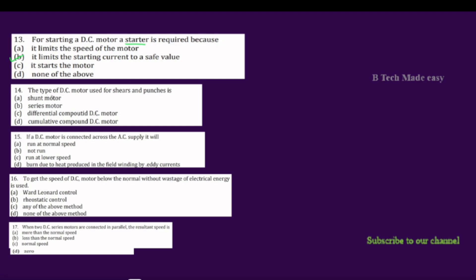Next question: What type of DC motor is used for shears and punchers? The four types of DC motors are: shunt motor, series motor, differentially compounded, and cumulatively compounded. The DC shunt motor is a constant speed motor — its applications include elevators, machine tools, and blowers. The DC series motor is used for electric traction and electric locomotives due to its high starting torque. Low starting torque applications use other types.